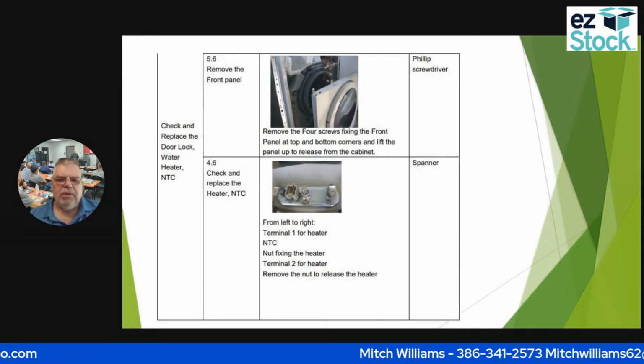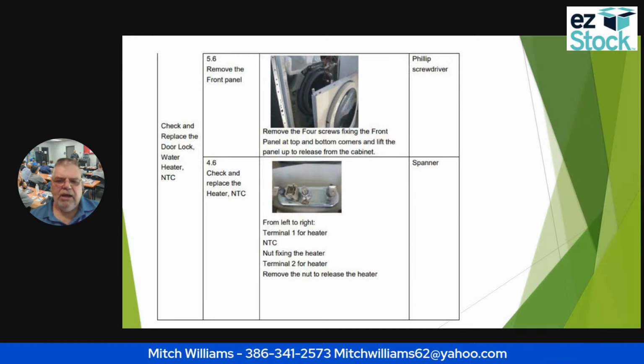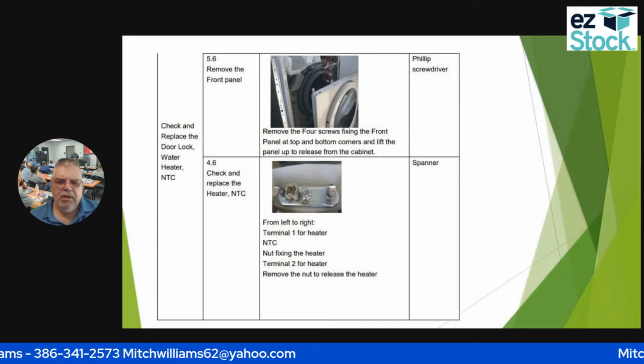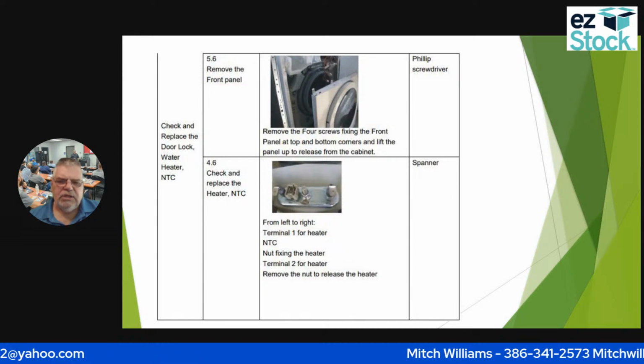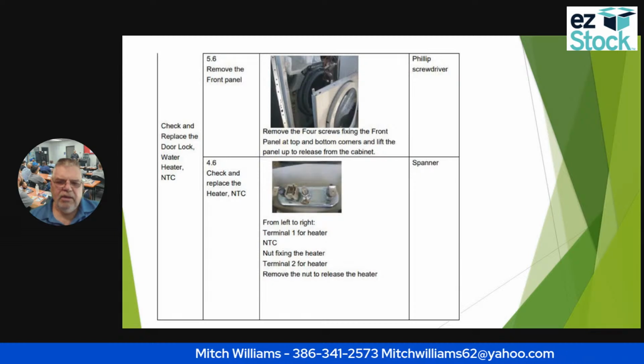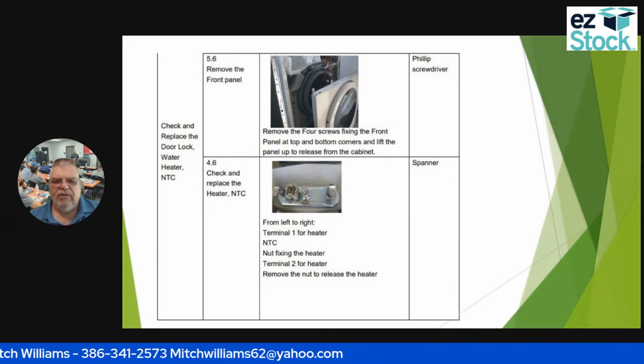Okay, check and replace the heater NTC. That's what we're already talking about. From left to right, terminal 1 is for the heater NTC. Nut affixing the heater, you can see that one. Then terminal 2 is for the heater. And then remove the nut to release the heater. So to take this off, I have to unscrew this nut right here.